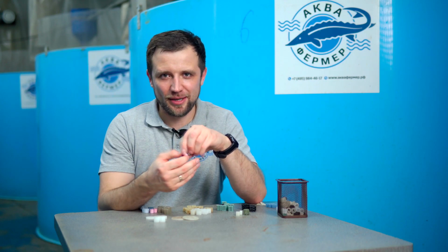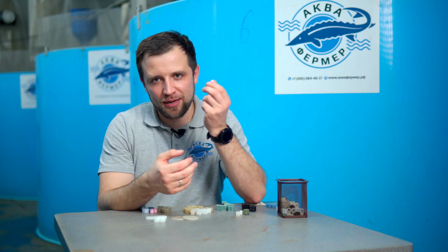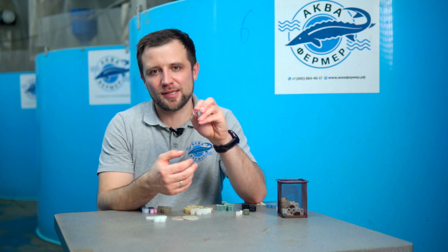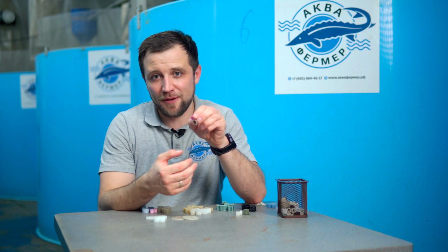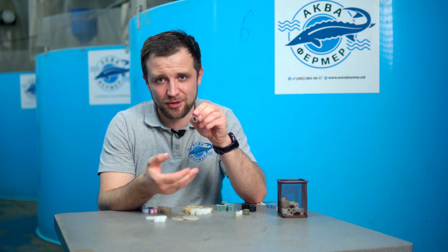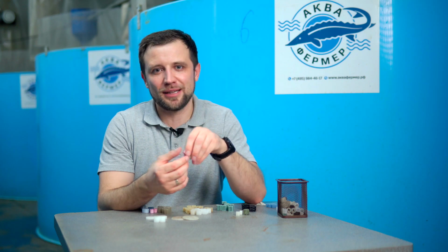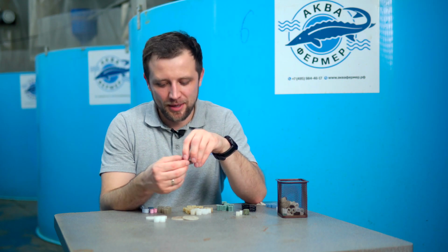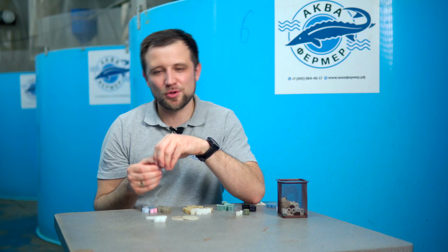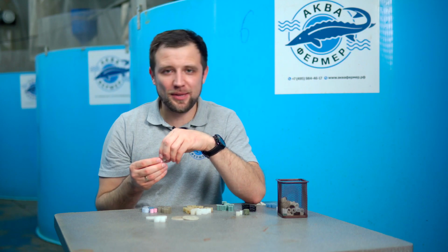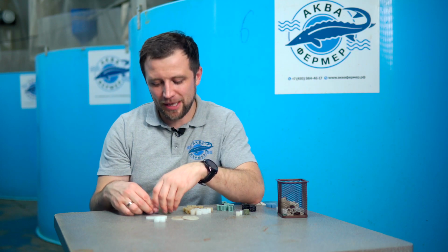Generally, we could tolerate all that. But there is also a problem that recycled materials often have bad microorganism attachment. That is, our biofilter simply did not start up. It really happened. And besides, recycled materials can smell. That's true. That's why we have practically given up using this media, though it's cheap.